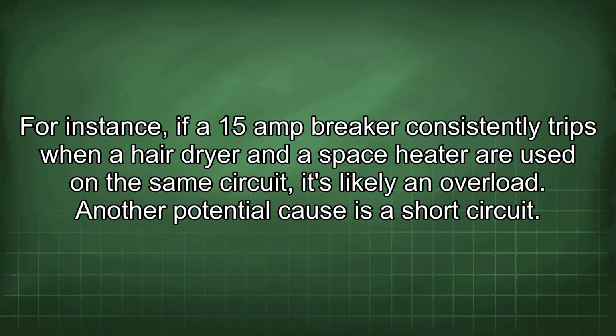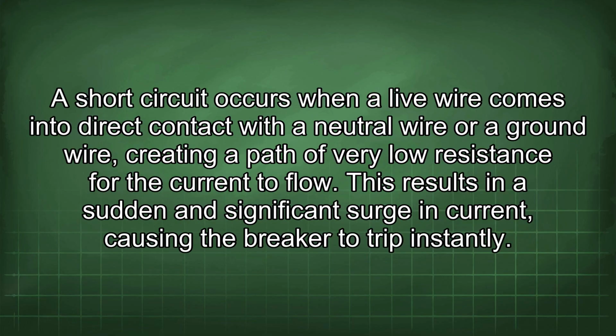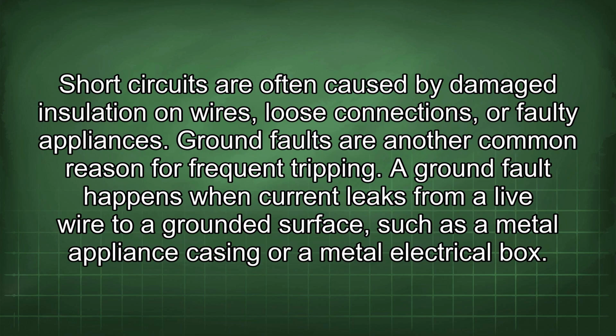For instance, if a 15-amp breaker consistently trips when a hairdryer and a space heater are used in the same circuit, it's likely an overload. Another potential cause is a short circuit. A short circuit occurs when a live wire comes into direct contact with a neutral wire or a ground wire, creating a path of very low resistance for the current to flow. This results in a sudden and significant surge in current, causing the breaker to trip instantly. Short circuits are often caused by damaged insulation on wires, loose connections, or faulty appliances.